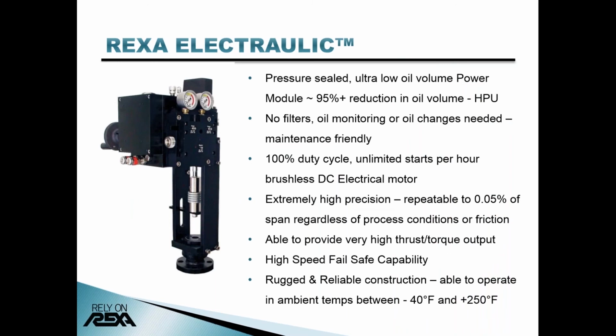Okay, let's talk about some benefits of the trademark name Electraulic actuator. To start with, it's a very unique design unlike anything on the market today. The true closed-loop hydraulic system is pressure sealed with oil volumes approximately 95% less than those found in a standard HPU. There are no filters or oil changes required, making it very maintenance friendly.